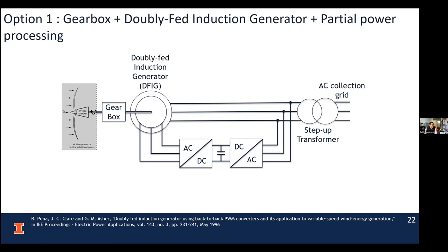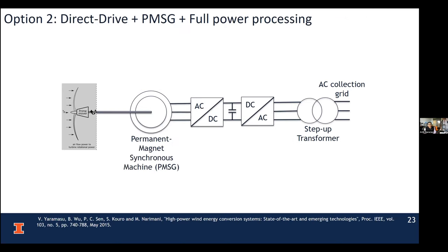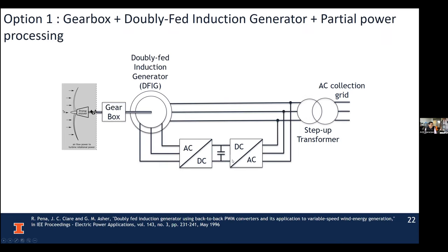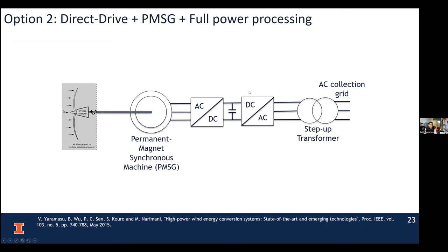So people went on to look at the second option: permanent magnet-based machines. What do we do here? It's a single port machine. Unlike in the doubly fed machine, there are permanent magnets on the rotor, so you don't need any electrical connections. On the stator, there are three ports. Now, the sacrifice we're making is instead of having partial power processed by back-to-back converters, we need full power processing done by this active rectifier. So if there's a 10 megawatt wind turbine, our AC to DC or DC to AC converter has to process 10 megawatt. That's it.